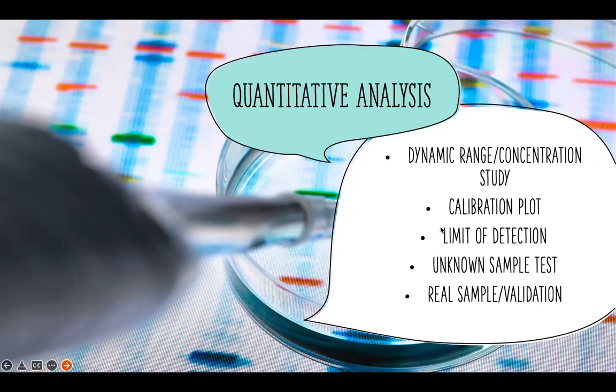And then identify the limit of detection. It means how low the sensor can detect, how low the concentration of the analytes of interest you can detect. And also, we have to test whether the calibration plot is good by introducing unknown sample types. It means that you can probably use real sample, or you can use spike sample.